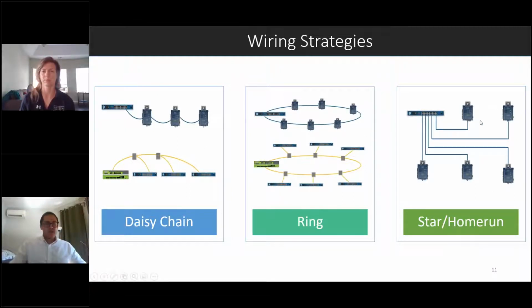Then finally, if you have some major piece of equipment that you really want to be on its own link, and you don't want to have it daisy chained with anything else, you do have that ability with Ethernet to home run that back to your central point, your Ethernet switch. So a lot more strategies available with your BACnet over IP communication. As you can see, you have both ring and home run wiring strategies available with BACnet over IP, whereas with BACnet MSTP, the only real wiring strategy you have is the daisy chain.